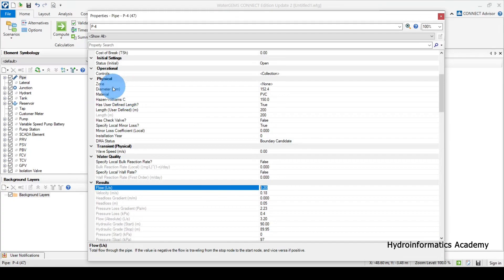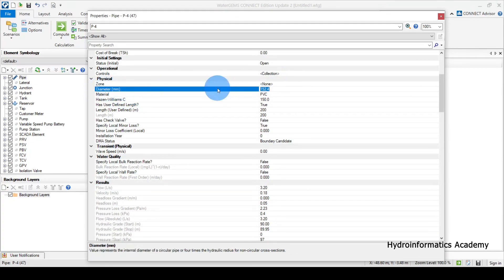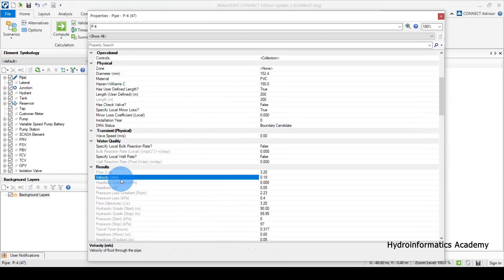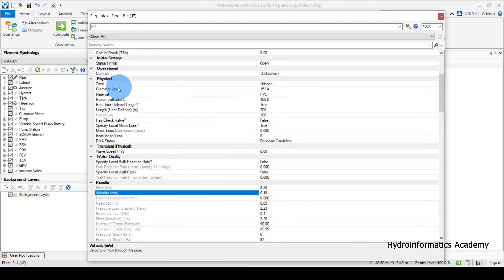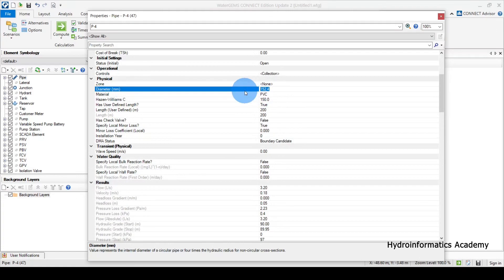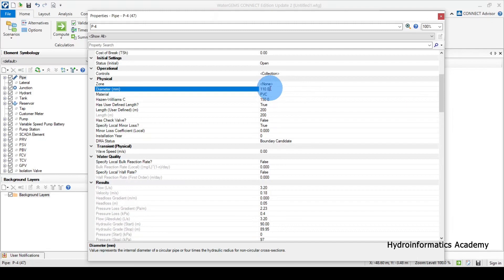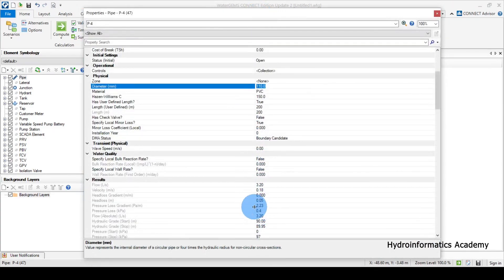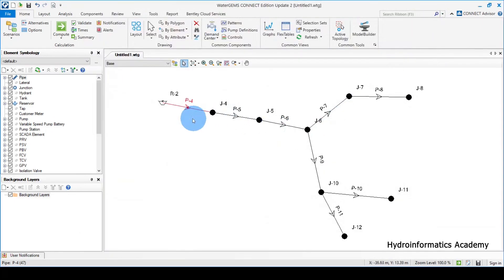Currently the pipe diameter is 152. I need to reduce this pipe diameter to increase head losses and hence increase the velocity. Let me take it down to 110. Remember, the pipe diameter you use here is not the commercial or outside diameter — make sure you are using the inside diameter of the pipe. Let me select this and check if velocity has increased.